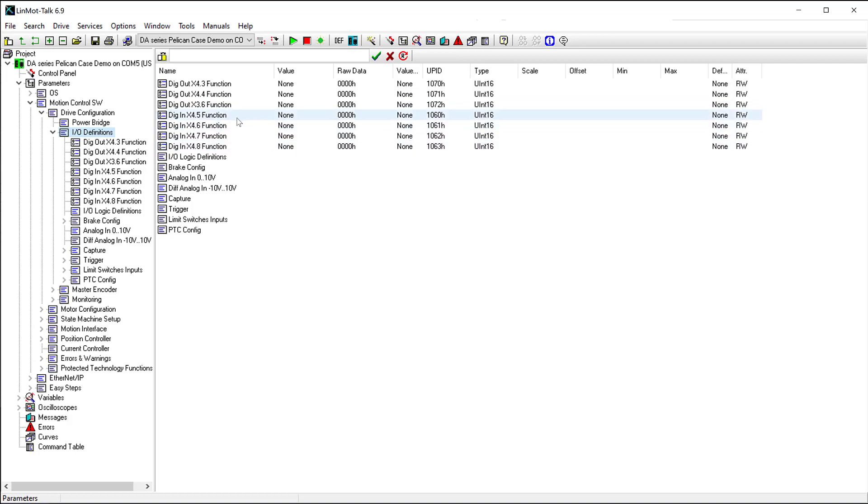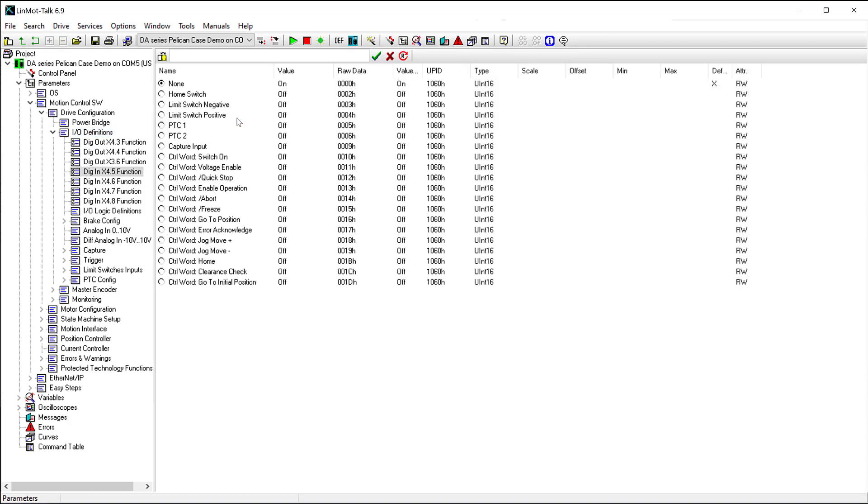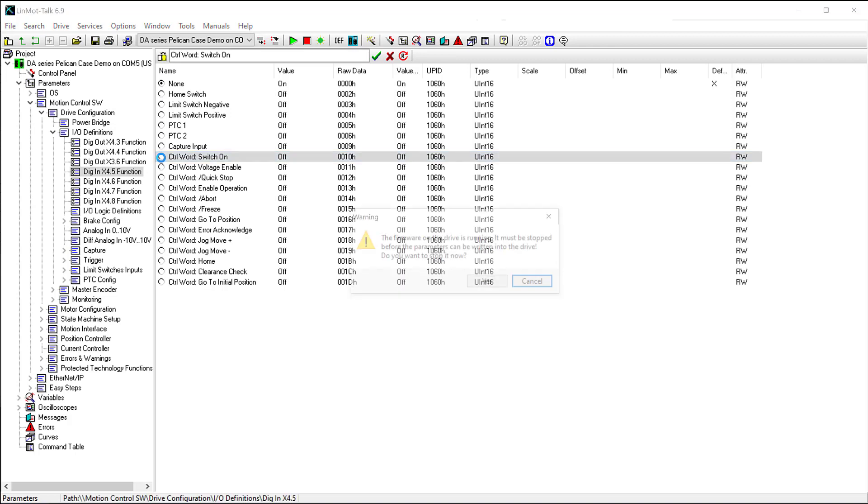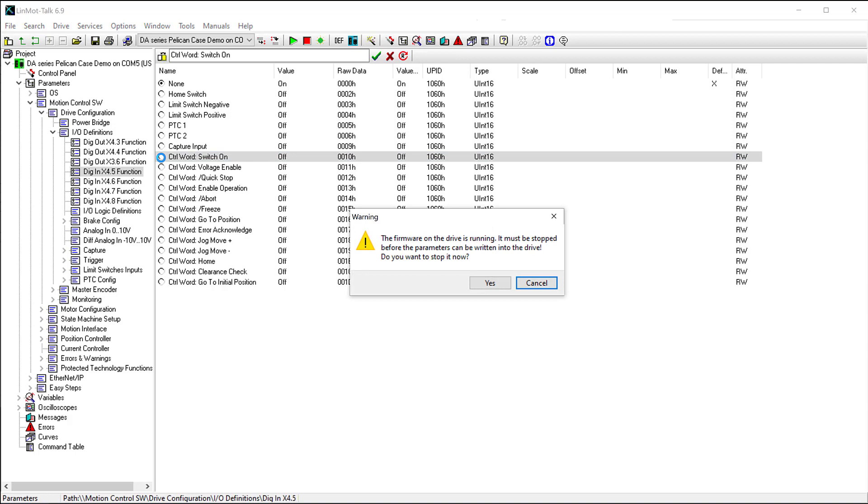We will start by going to input X4.5. We will set this up as the switch on bit in the control word. This will allow us to turn the drive on and off using a discrete input. To select this option, double click the empty circle next to control word switch on. A dialog box appears telling us that we must stop the firmware to make this change. Click yes.